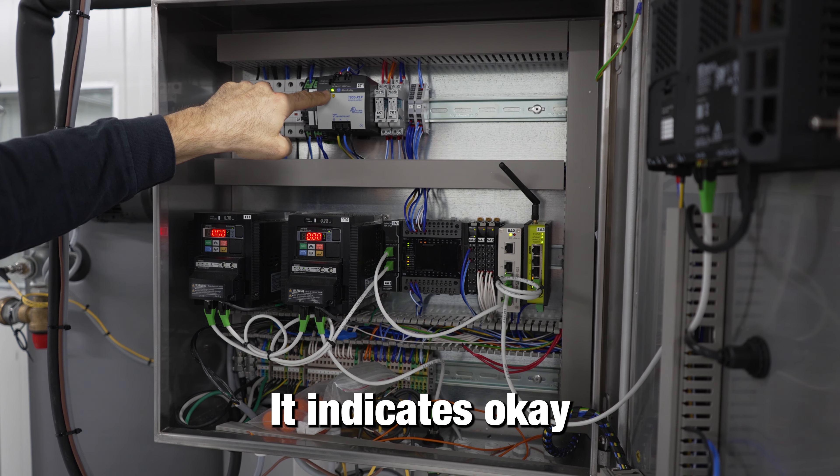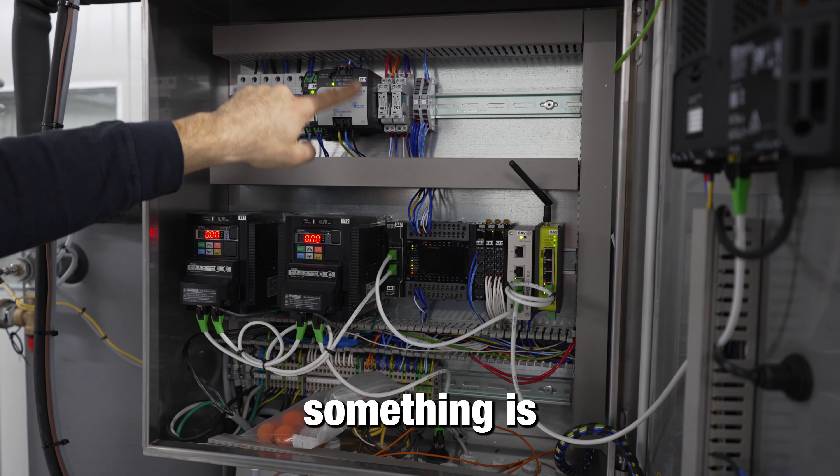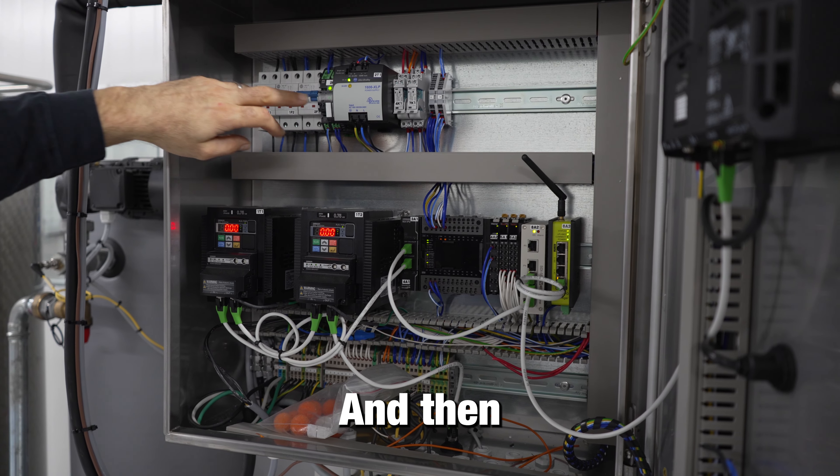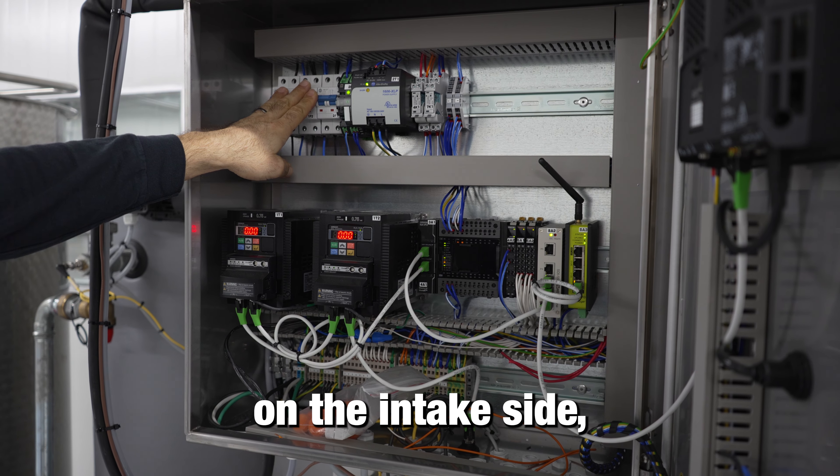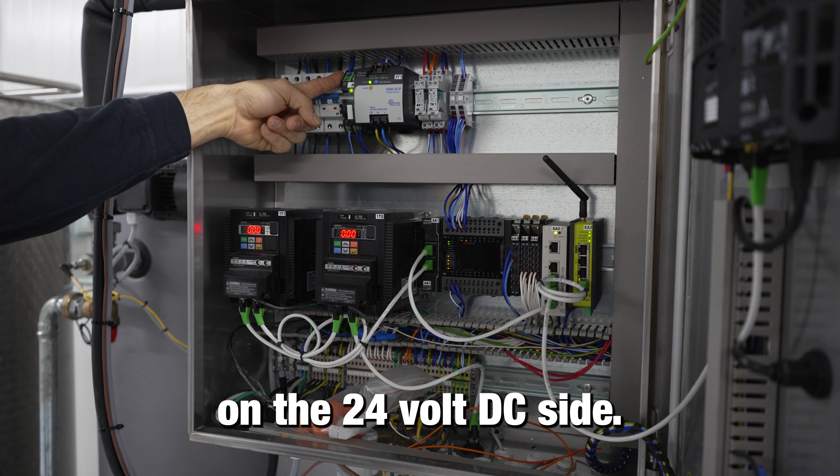All of that runs on 24 volts and that basically goes in at 220, comes out 24 volt DC. It indicates okay with the green light. If that light is not green, something is wrong with this, and we have a breaker on the 24 volt DC side.